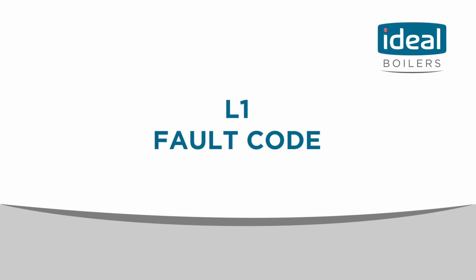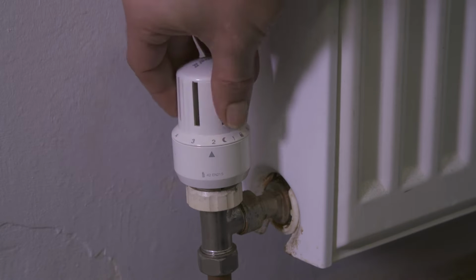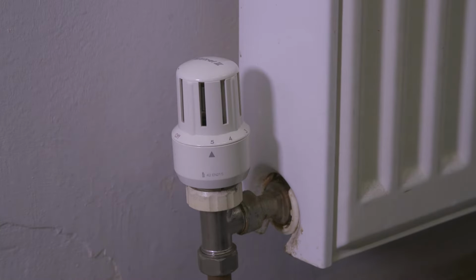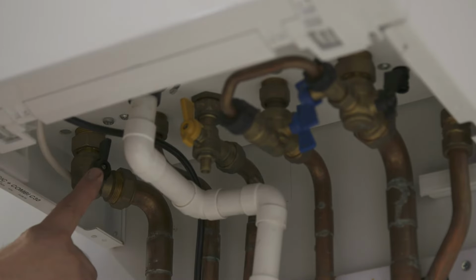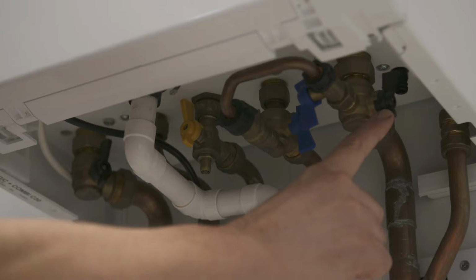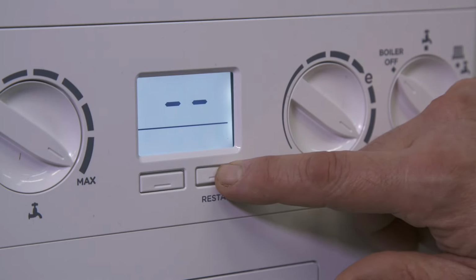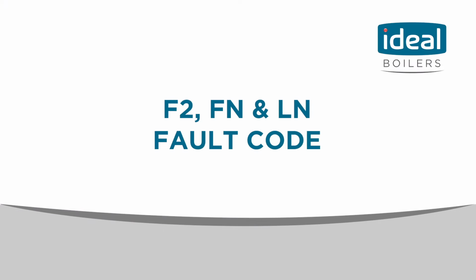If you do encounter an L1 fault code, ensure all the radiator valves are in the open position and the isolation valves underneath the boiler are also in the open position. If they are in the open position, press the restart and see if the fault clears. If the fault persists, contact Ideal Boilers.